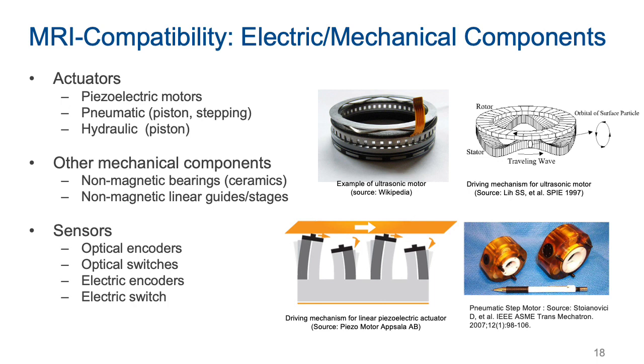Every electric or mechanical component must be compatible with the MRI environment. There are several types of actuators that can work in the MRI environment, such as piezoelectric motors and pneumatic motors. Unlike regular magnetic motors, these actuators do not use magnets to generate torque. Other mechanical components like non-magnetic bearings or linear guides are also used to make the device compatible with the MRI environment. Encoders and switches must be made of non-magnetic components and must not release EM noise into the MRI environment. In some cases, signals from encoders and switches are transmitted to the controller via optical fibers to ensure this, but they may be wired with electric cable as long as the cables are properly shielded and filtered.